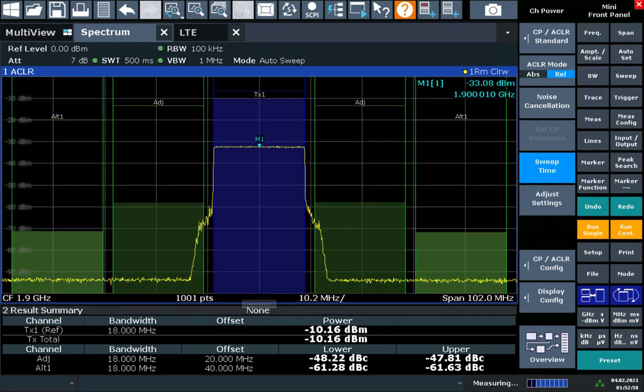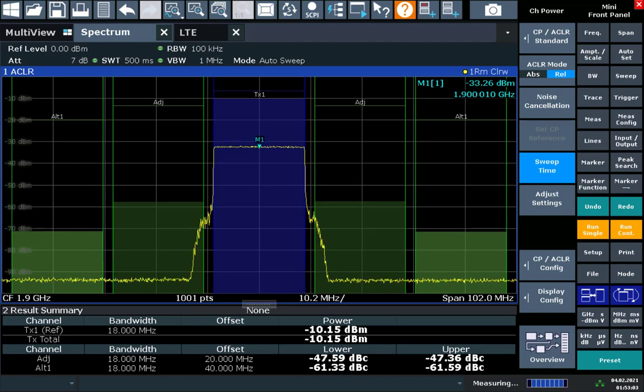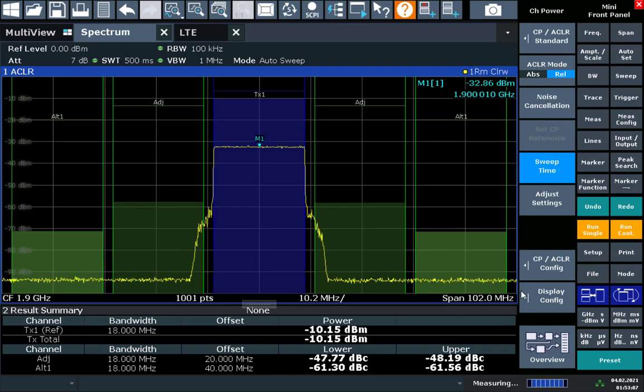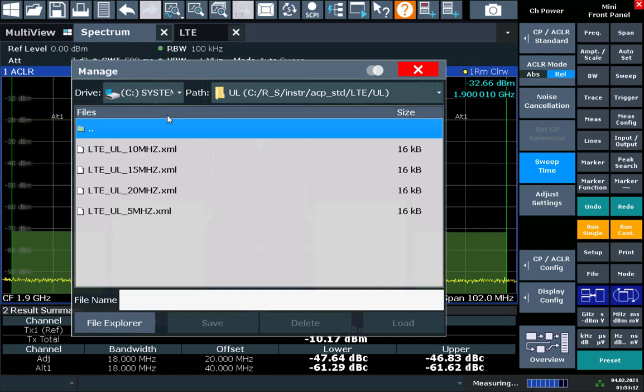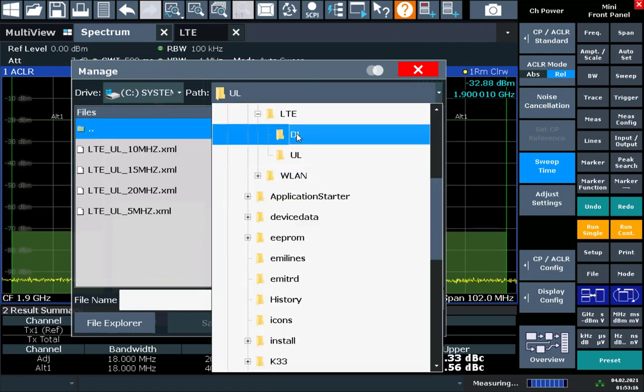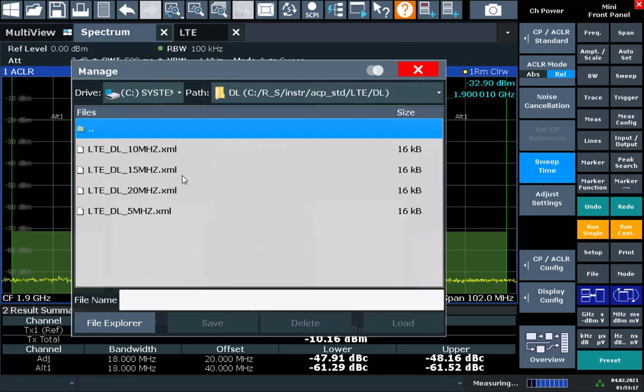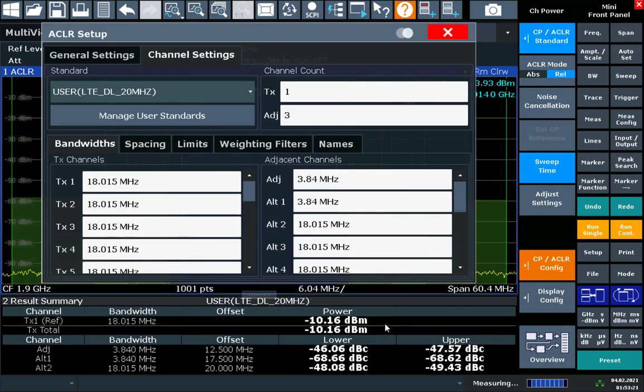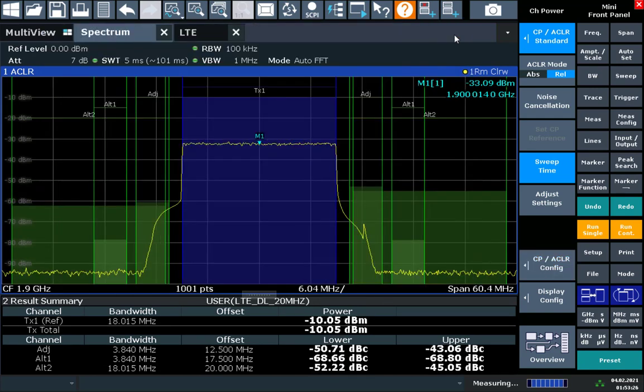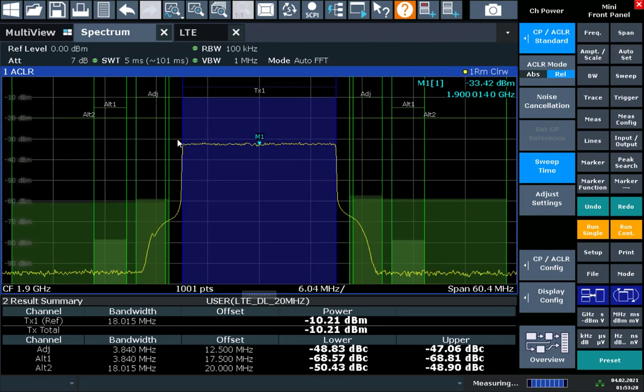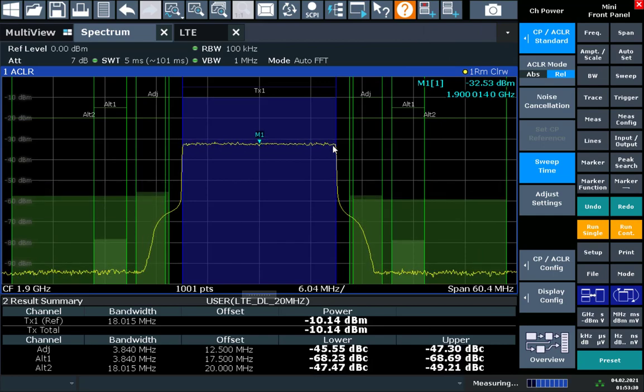In fact, if we're doing an ACLR measurement on a standard signal, we don't actually need to configure the bandwidth and spacing on our own. We have those built in as presets. So we can go to CP ACLR config, manage user standards, and we can navigate to LTE downlink, 20 meg. Go ahead and load that predefined XML file, which is shipped with the instrument. And now we have a 20 MHz channel.